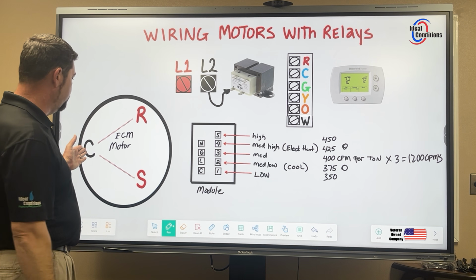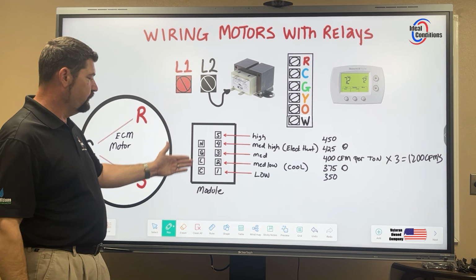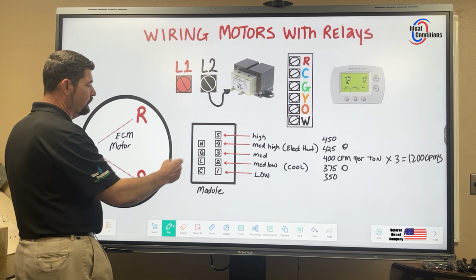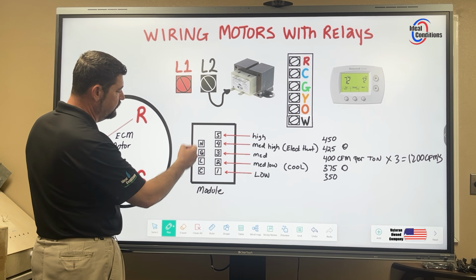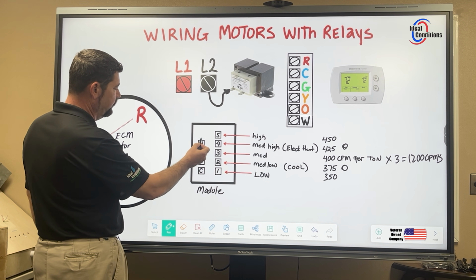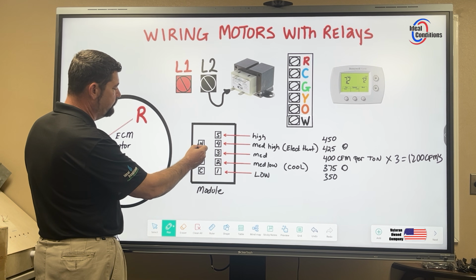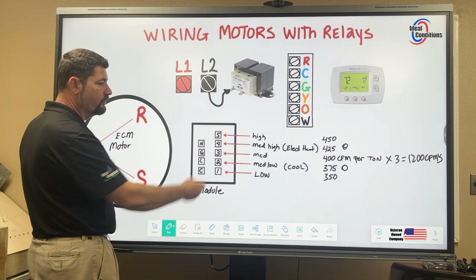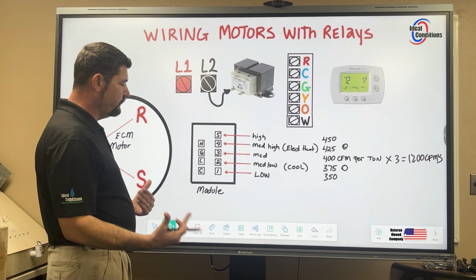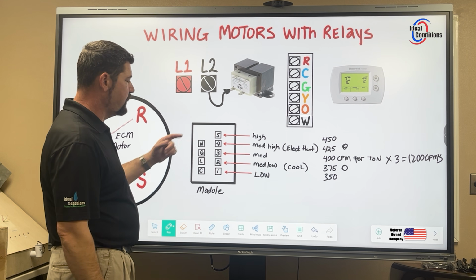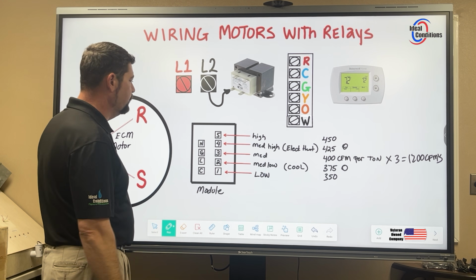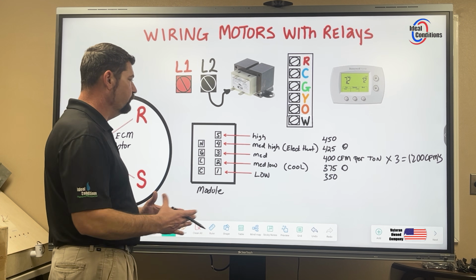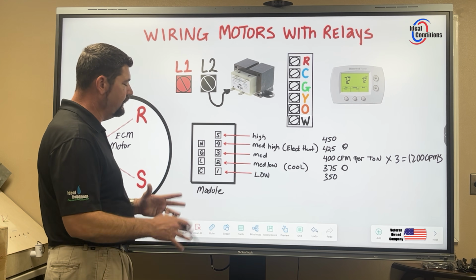Well, L2 has to make it to common, but it's going to first have to go to my module. So I'm just going to pick N just because N is a high voltage tap. I did show you that N could also be neutral. However, a 230 volt motor, you're not going to wire N to neutral because you're not going to get the proper ampacity, and those motor windings were not designed for that, and it will eventually fail.